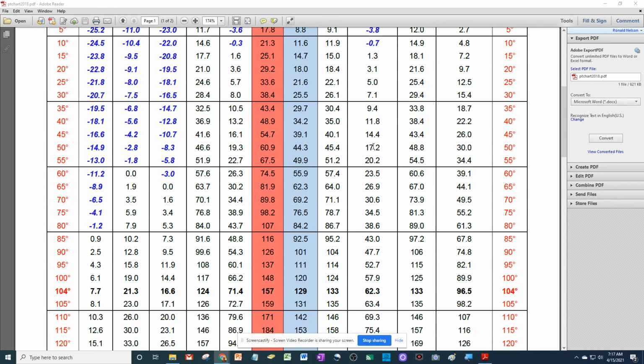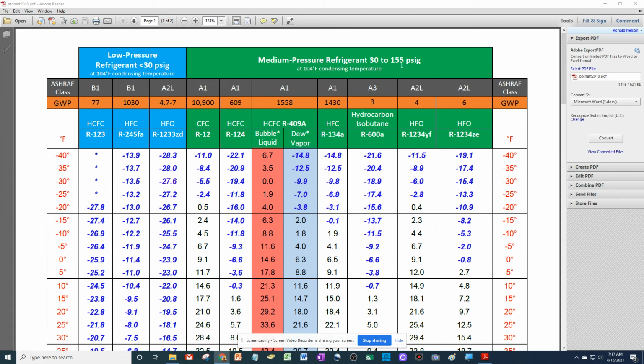For instance, if they gave you a medium pressure refrigerant, the same way. But hey, let's say 134A, all right? What is its vacuum rate? And it says it's got more than 200 pounds of refrigerant. Okay, so it's medium. It's more than 200. So that would be 15 inches of vacuum. So it can help you answer those questions.